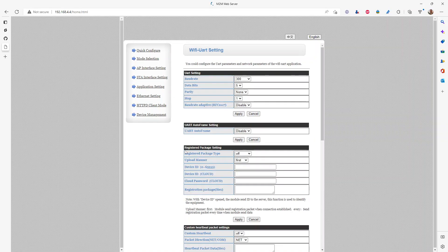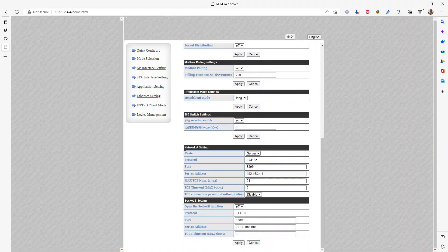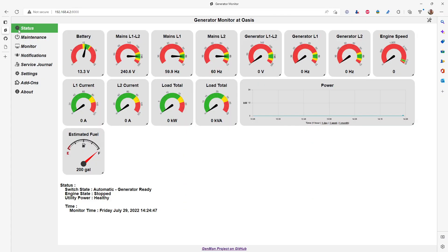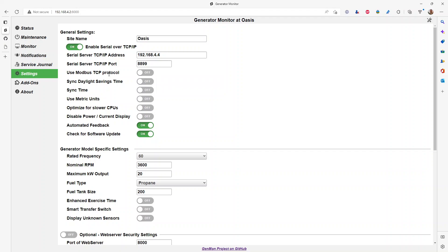To allow the Raspberry Pi to connect to the device, you need to, in the network setting down here, set up this device as a Modbus server. Note the port. You can make that port whatever you want. You just need to know what it is, and note the IP address of the device. In Genmon, you'll enter that same information on the settings page. Enable serial over TCP IP. Pick the IP address of the converter device and the port. And if you use the transparent mode, nothing else needs to be done. If your device does not support transparent mode and needs Modbus over TCP, you'll enable this setting.